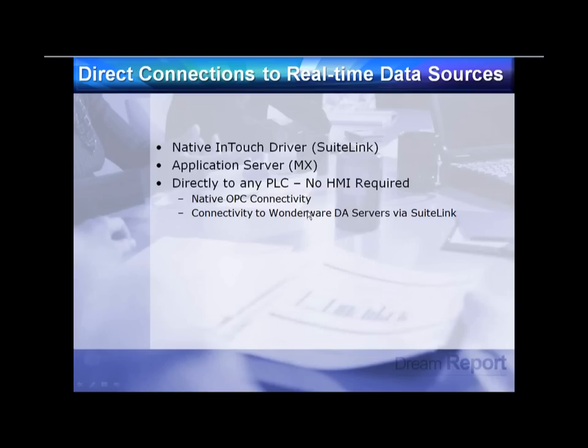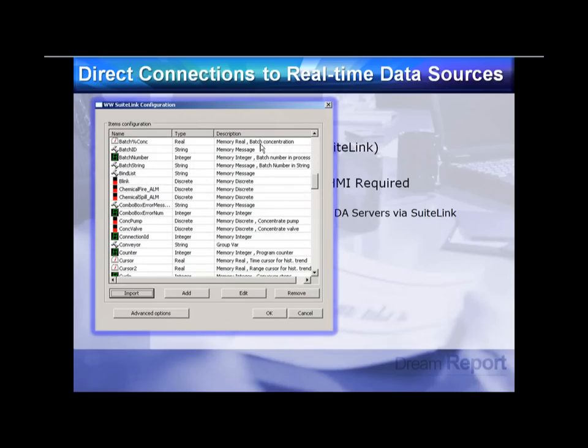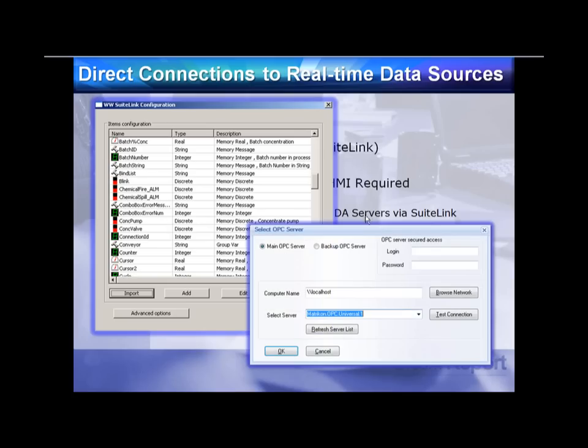For real-time Wonderware data sources — InTouch, Application Server, or directly to a PLC — several options are available. The SuiteLink driver exposes the entire InTouch tag name dictionary so you can pick which tags to log and report against. For any OPC server, whether a Wonderware DA server or third-party, DreamReport supports browsing and connection, as well as OPC DA, alarms and events, and HDA historical data access OPC servers.